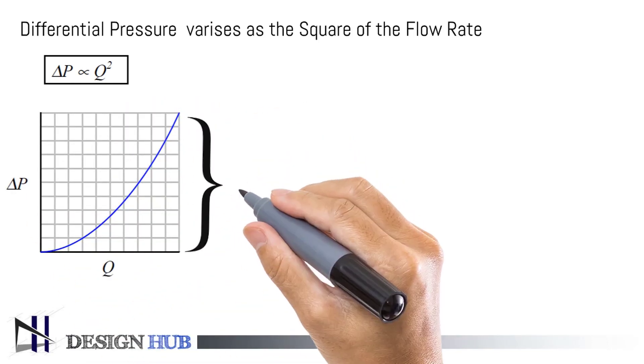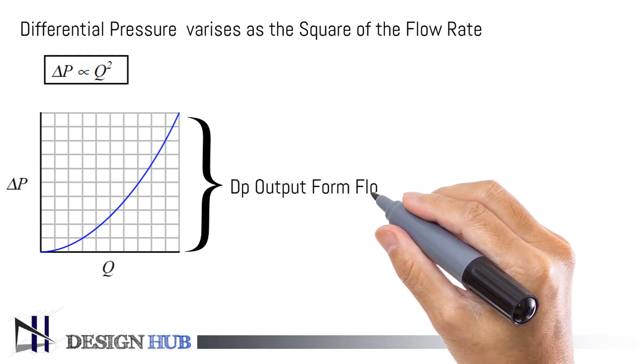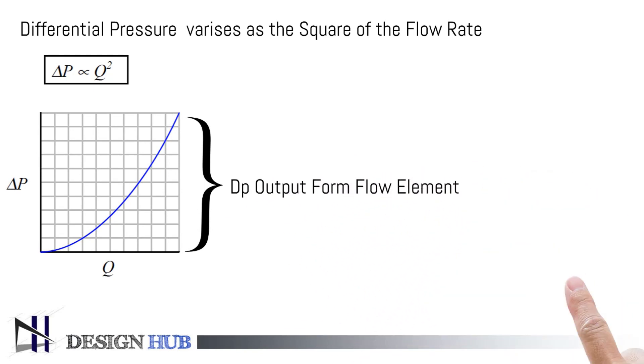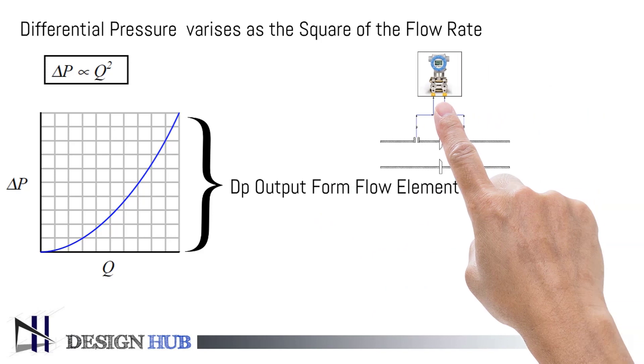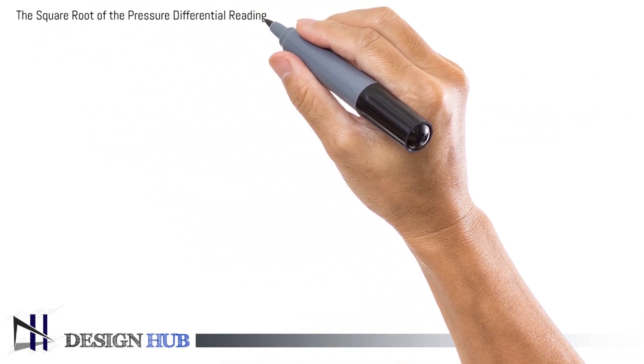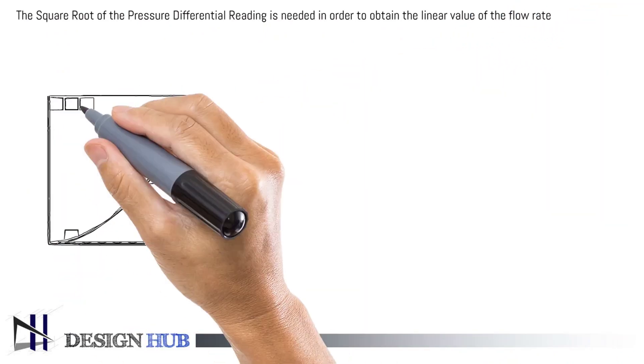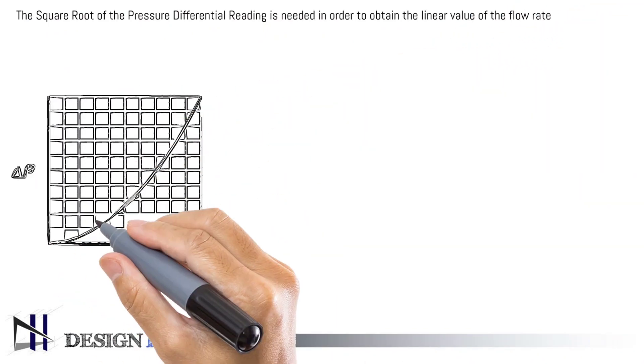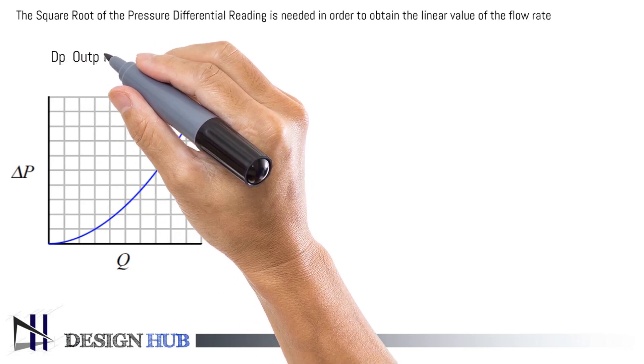This output is directly received from the differential pressure flow element. Then the square root of the pressure differential reading is needed in order to obtain the linear value of the flow rate. This is the DP output from the flow element.